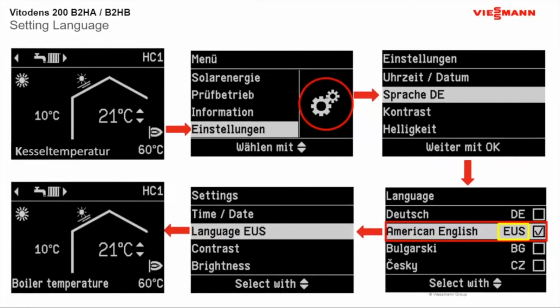So like I was saying, prior to the startup wizard coming out, this is the way you would get the boiler. You would get it in German. And you would have to do all of this changing once you got the boiler. So it came in Celsius, and you know, we are the only country that does Fahrenheit. I get that, but whatever they made, we got here. And so you would have to go in there and change it. So if you didn't understand German, that's boiler temperature there. So what we're looking at, it says to go into and look for this word here.